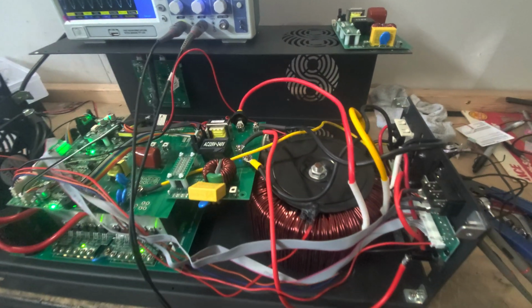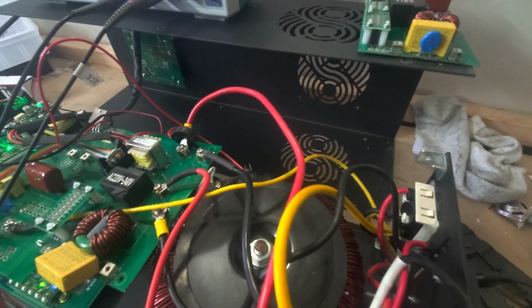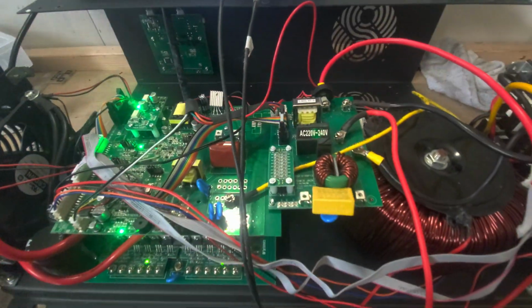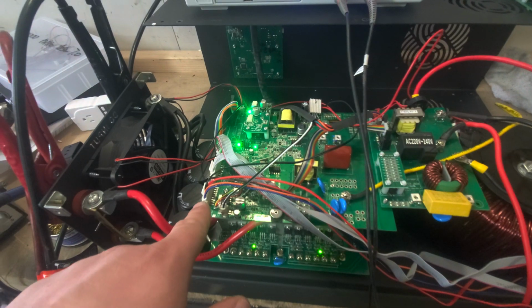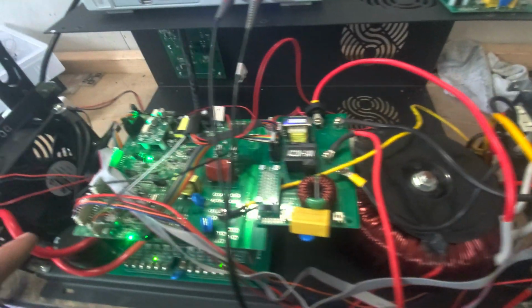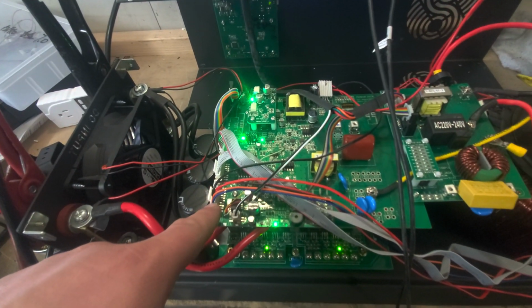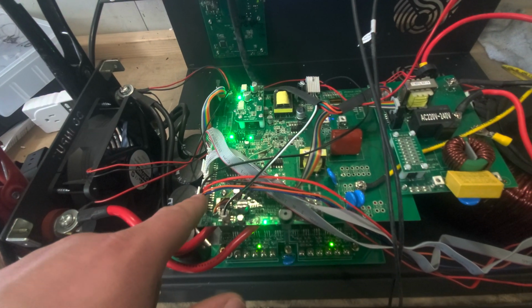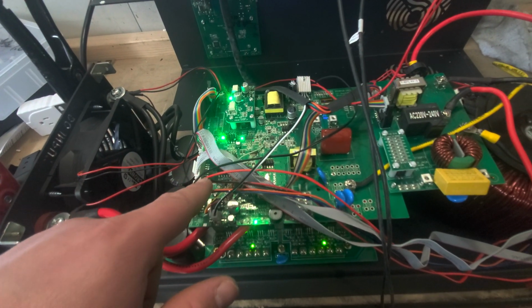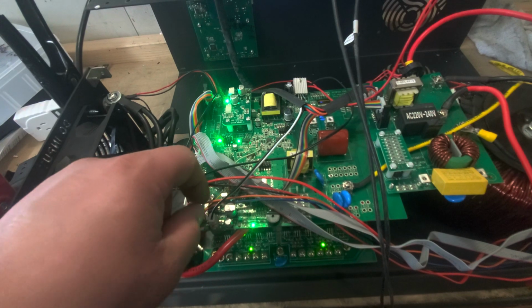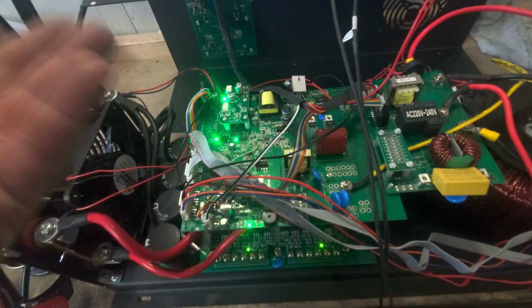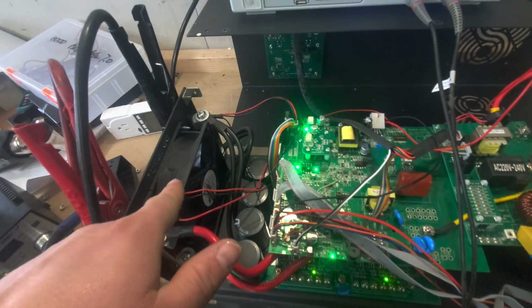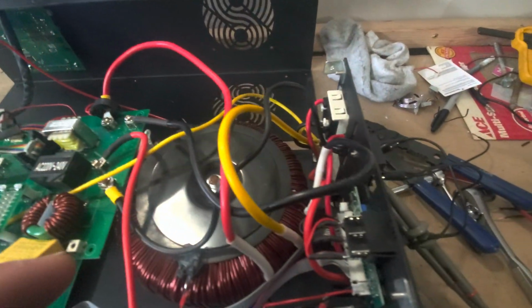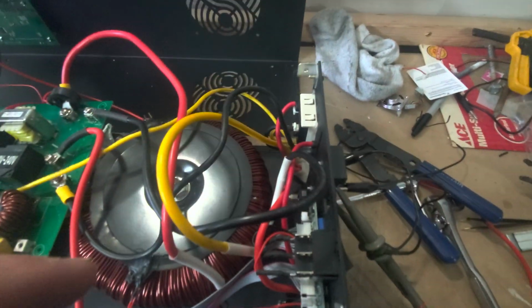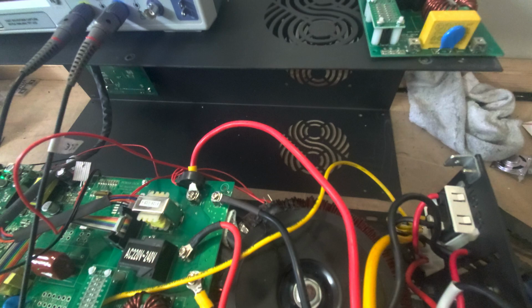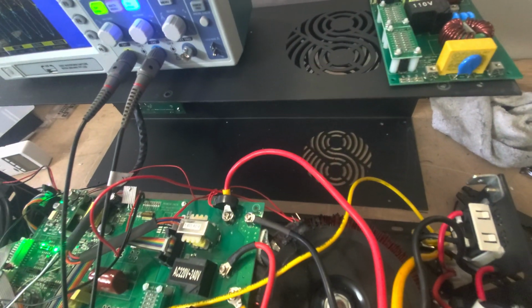This inverter will need the fan harness in order to complete this. Basically, you're taking a harness. You can actually do it two ways. This orange and blue wire here is actually the manual fan controls. But it just depends on the board. If the new board is not capable of controlling this fan right here, then you basically have to do the manual override, which is as simple as shorting these two connectors out.